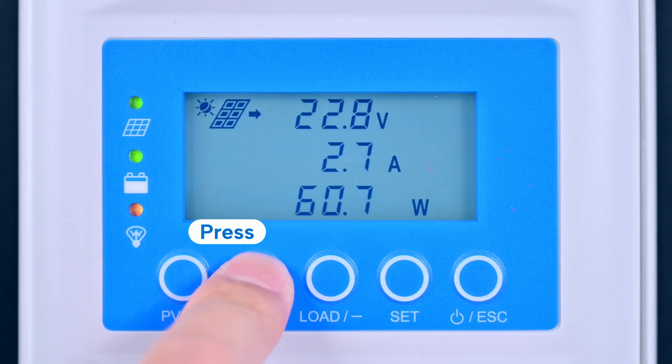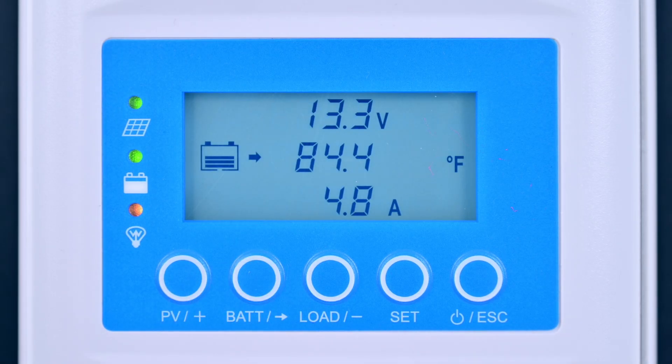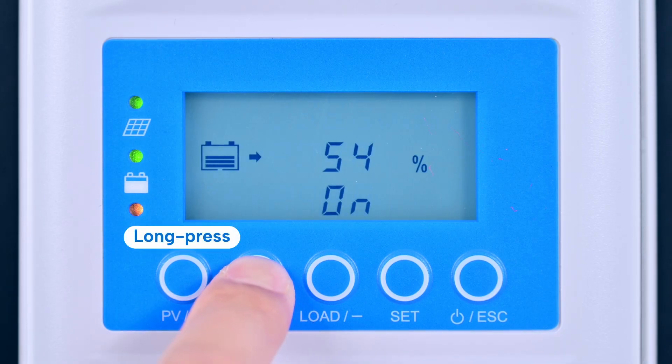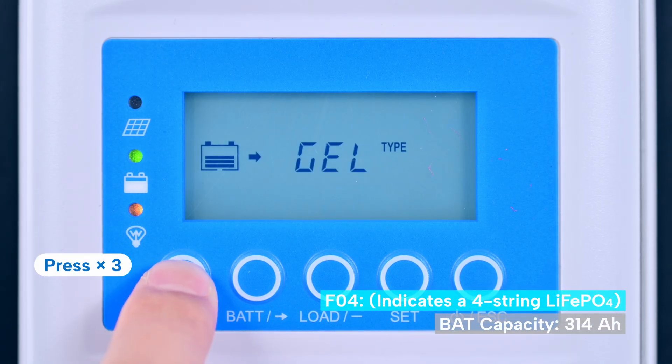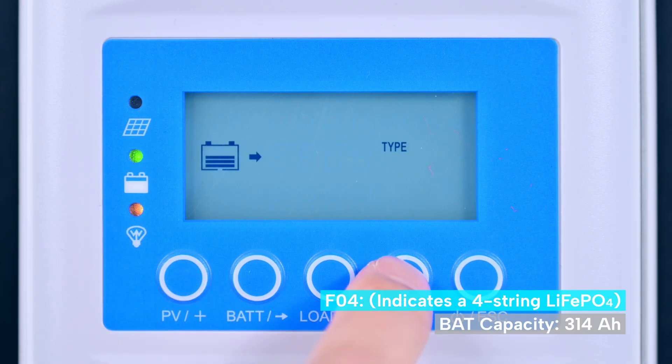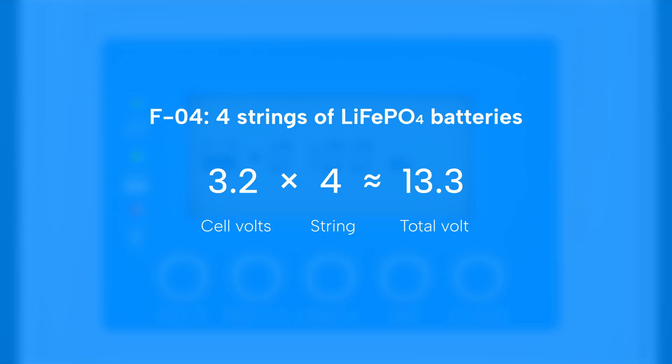First, press BAT to view battery parameters. Then, long press BAT to enter the settings. The default setting is sealed lead acid battery. Change it to a four-string lithium iron phosphate battery. F-04 means four strings of LiFePO4 batteries. Each battery cell delivers about 3.2 volts. Four cells together give approximately 13.3 volts. Make sure your battery type and string number settings match your actual battery configuration.